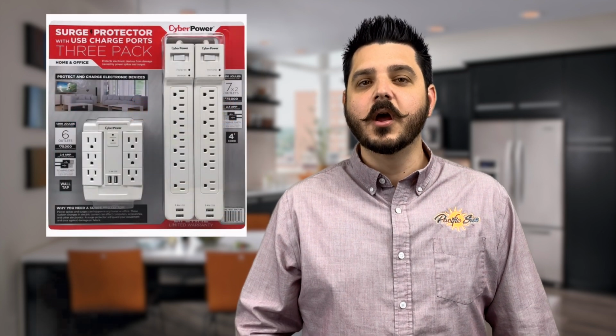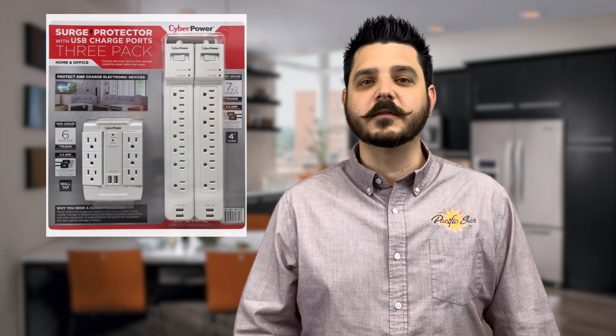Surge protection: what is it and how does it work? To better answer that, we need to break protection into three types. There's type 1 protection, which occurs at your main service panel meter; type 2 protection, which we install for homeowners regularly at the electrical panel; and type 3 protection, which you can install yourself.